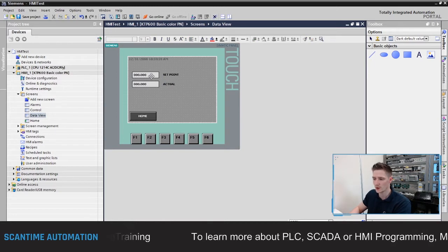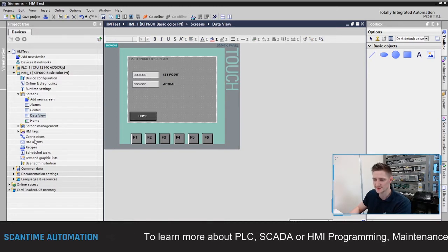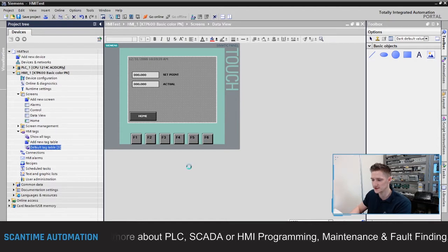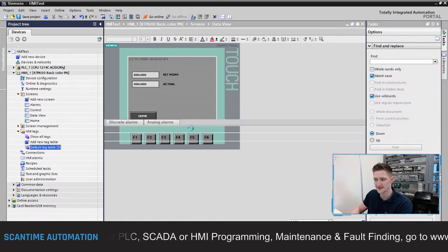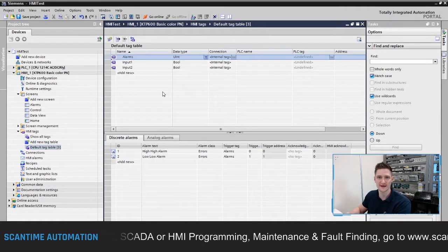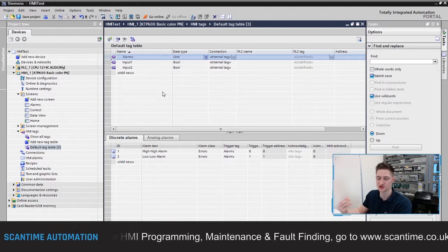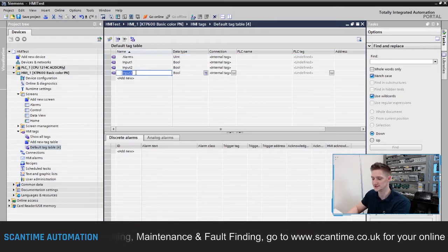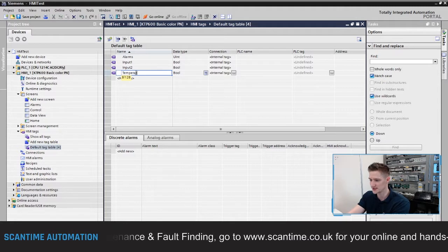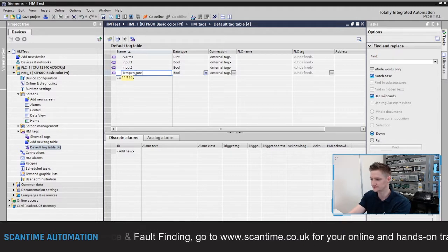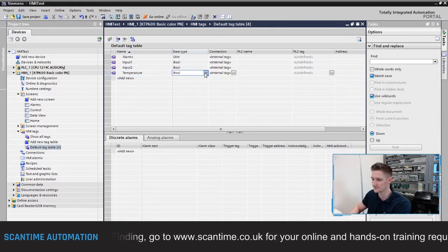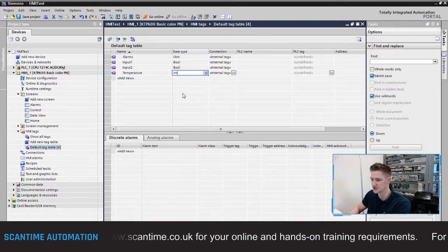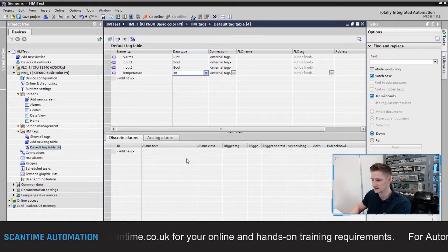Now I'm going to go to my HMI tags, open up our default tag table, and create an integer that will display a value — in this case, temperature. I'll type in 'temperature' and set the data type to INT.